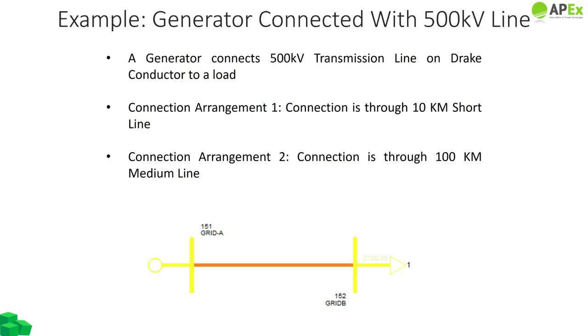We have created two scenarios. Both scenarios have something in common: a large generator connects through a 500 kV transmission line to a load, and this transmission line uses a Drake conductor—remember the one I told you to remember in the previous slides on thermal limits? In the first connection arrangement, the line connecting the generator to the load is 10 kilometers long on the Drake conductor. This is example 1.